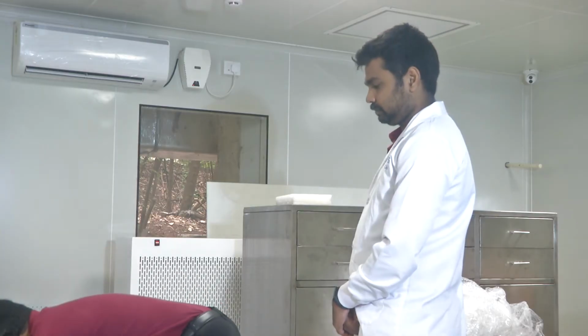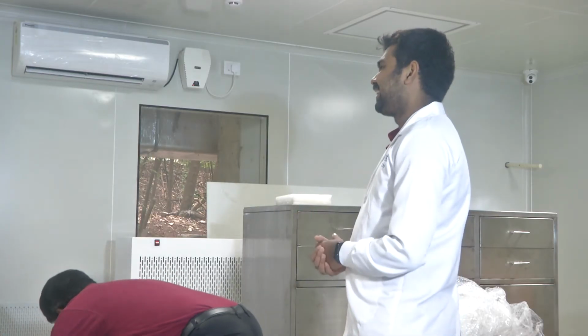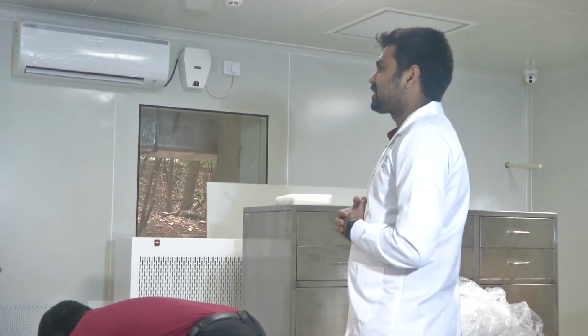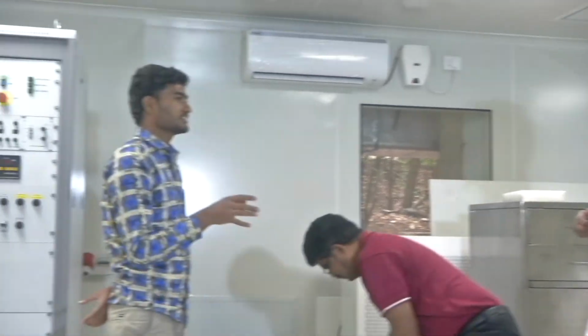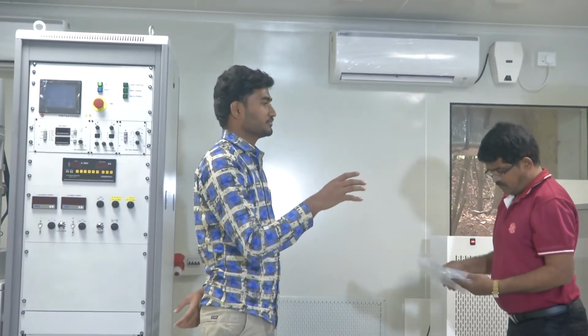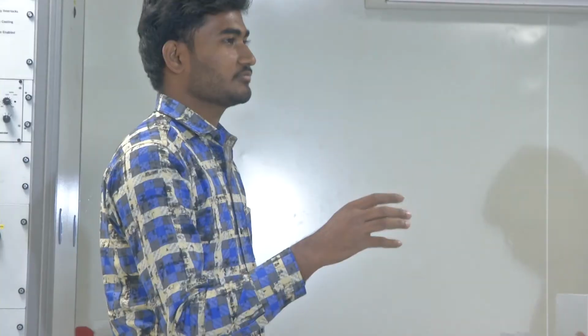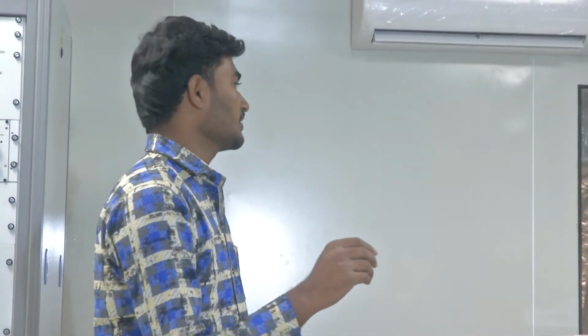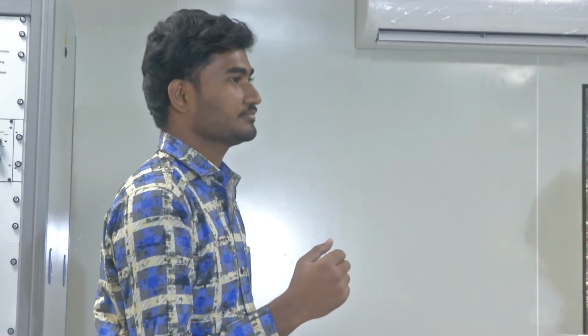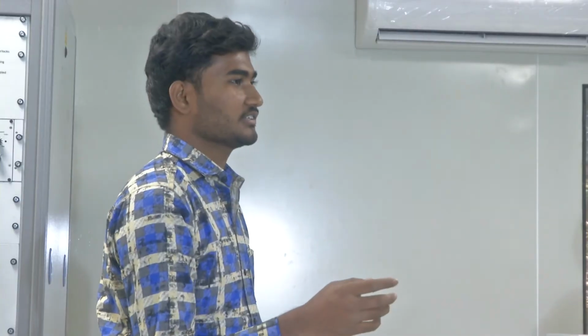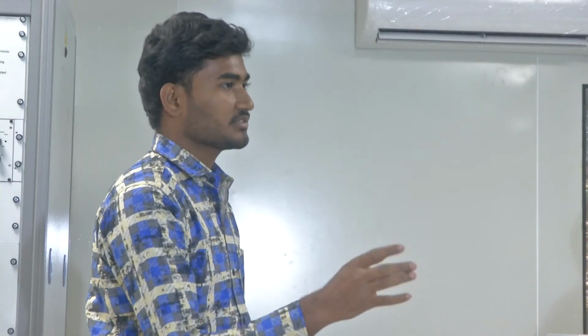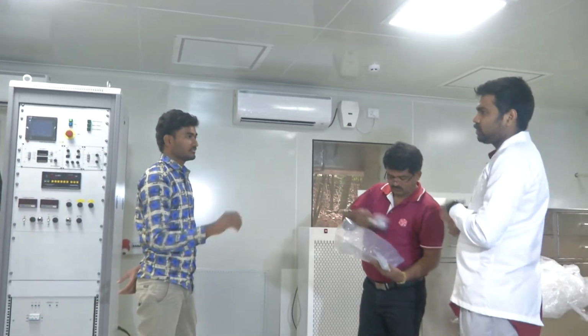Suppose if there is any error, you can correct for it, otherwise you can use it normally. But how will we know an error is there? Because that is the one that is telling us the pressure. To measure that, a master gauge is required. But here it is not available. You can identify errors easily at certain times. We know that in the process, after half an hour, we should reach this pressure, and it is not showing that pressure.